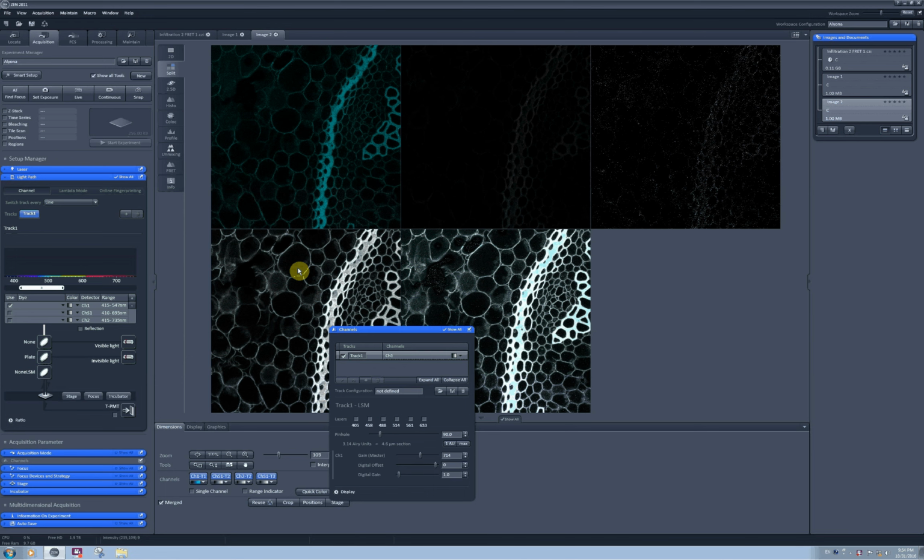Track two would be for excitation and detection of YFP and Alexa 680. And track three will be for detection of sensitized emission of YFP, where you use excitation light for CFP and emission detection range for YFP. And the problem is how to keep this switch track every line option still available. I will configure now track one by one.